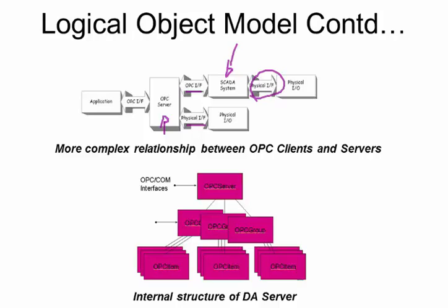It aggregates all of this information, its own physical I/O plus its own OPC interface, and presents it out on an OPC interface that our HMI or historian or something else is consuming. So everything's treated as an object. It's all client server in the OPC space.